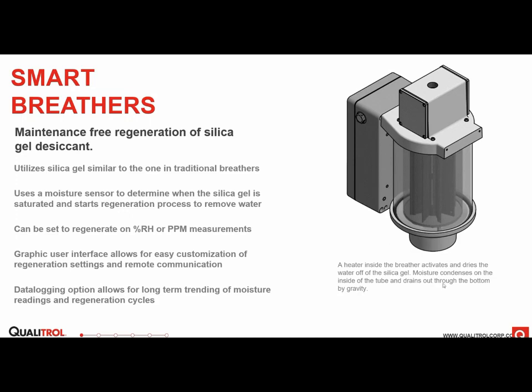And in this diagram here, you can see the way it's regenerated is that there's a heater inside the desiccant chamber. And in our case specifically, we have these aluminum fins that radiate that heat through the silica to get it up to temperature to drive out that moisture. And the moisture will evaporate or turn into steam essentially and condense on this outer tube and then drain out of the bottom.